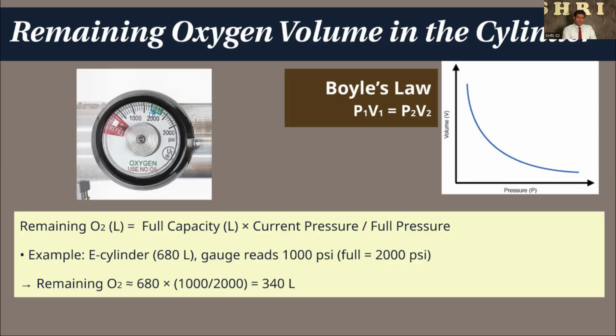When it is fully loaded, you can see 2000. When you see the 2000 mark, most people, our health assistants, say, "Sir, we have a cylinder with 2000 liters." No, this 2000 is in PSI units. So 2000 is the pressure index we use with a fully filled oxygen cylinder. That is the pressure level, but not the liters of oxygen.